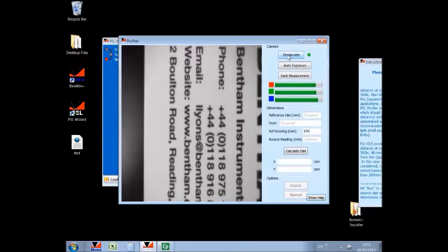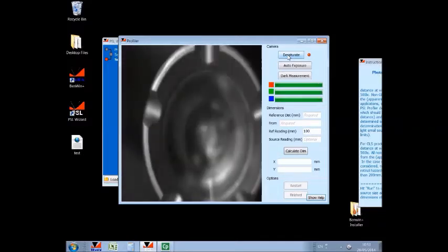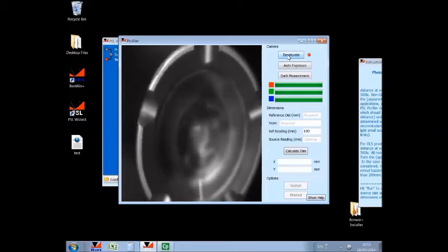So now the PSL Profiler is imaging a plane 200mm distant, and in the remainder of the procedure we should not touch the thumbscrew to adjust the position of the lens, and merely use the movement of the PSL Profiler to determine the distance from the reference point of the source to the apparent source where required. So at the 200mm position, I will put the reference point of my source under test.